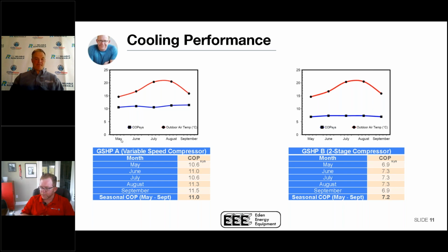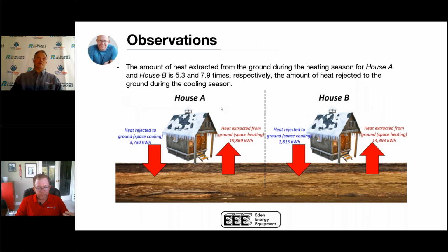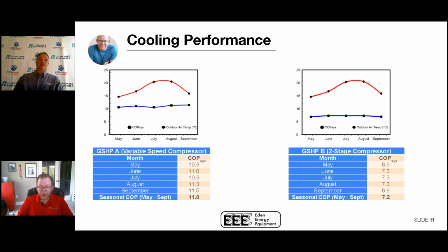And then the 2-stage compressor unit, you can still see at a seasonal COP of 7.2. So these are pretty impressive numbers, no question about that. Resilient to the weather and resilient to any changes in the climate, not driven by outdoor air temperature. A similar graph for other technologies would show both lines running parallel as the temperature goes up or down, the energy usage tracking directly in proportion, but not in this case.